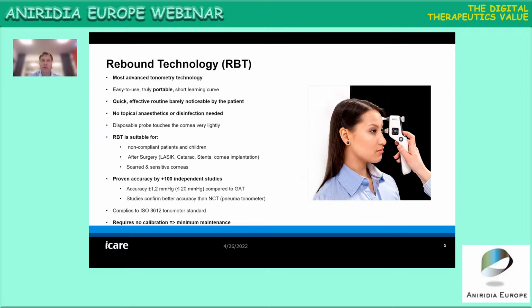Then I will explain the rebound technology. So the technology itself, we would say, is the most advanced tonometry technology, since it's the latest technology that has been introduced to the markets. It's really easy to use, it's portable, and using the tonometer usually needs a really short learning curve. The measurement is really quick, effectively and routinely barely noticeable by the patient. It requires no topical anesthesia and no disinfection, since the probes that are used in the tonometers are disposable and they touch the cornea very lightly.